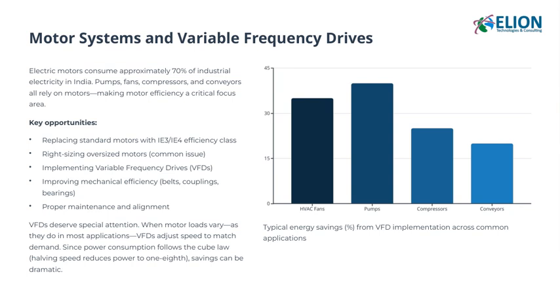Another important point is right-sizing motors. Oversized motors are common and often waste energy because they run at partial load, which isn't efficient. Implementing variable frequency drives, or VFDs, is another game changer. VFDs allow motors to operate at variable speeds, adjusting to actual demand. When loads vary, like in many applications, VFDs can dramatically reduce energy consumption. Because power consumption follows the cube law, halving the motor speed can reduce energy use to 1/8. That's a huge saving potential. In addition to these, improving mechanical efficiency by maintaining belts, couplings, and bearings further reduces energy waste. Proper maintenance and alignment are simple yet effective ways to keep motors running efficiently.